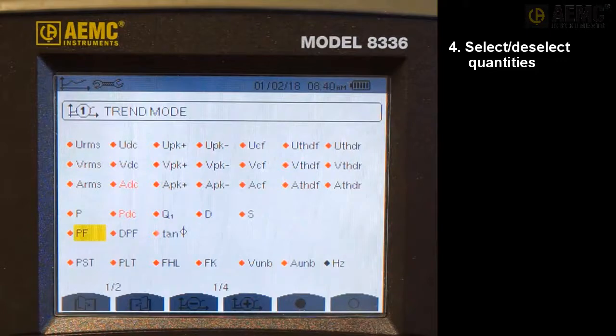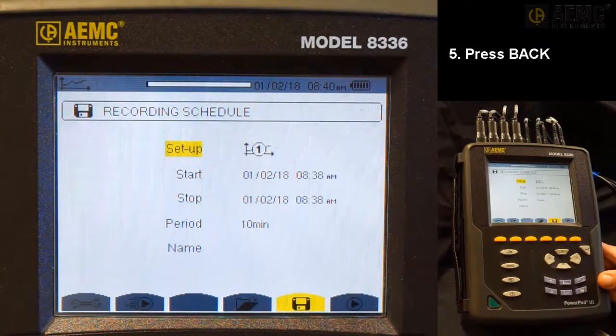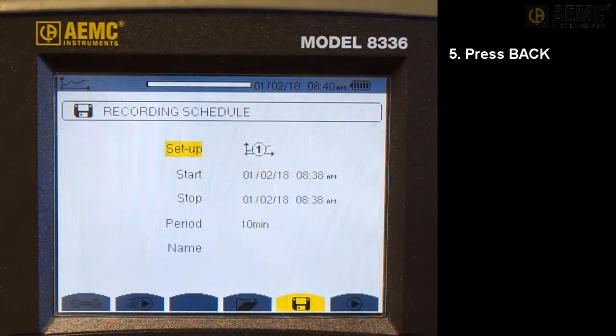Now we will schedule the recording. Press the Back button to return to the Recording Scheduled screen. This displays five input fields. Setup identifies the configuration preset, one through four. Start defines the time and date when the recording starts. This must be later than the current date and time. Stop specifies when the recording ends. This must be later than the start time. Period defines the aggregation period. This is the time over which the measurements are aggregated. Name allows you to name the test. This can be eight characters long.